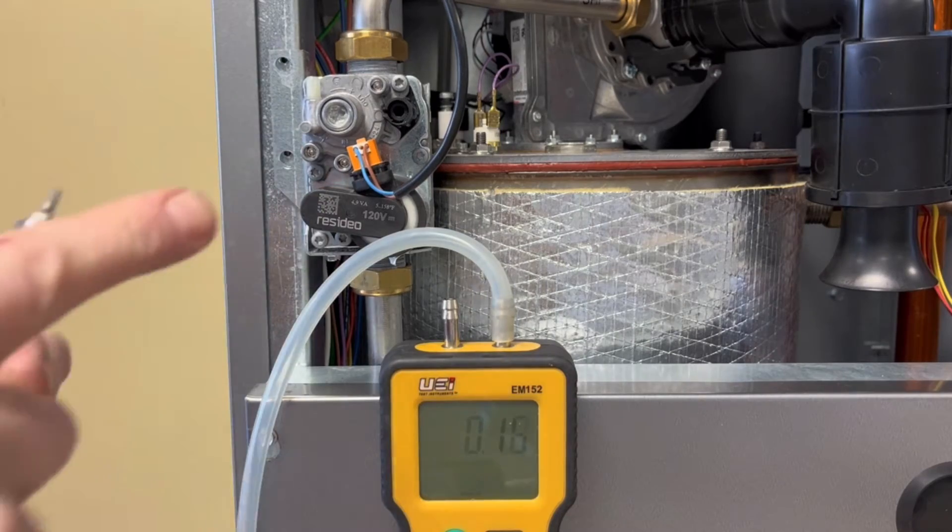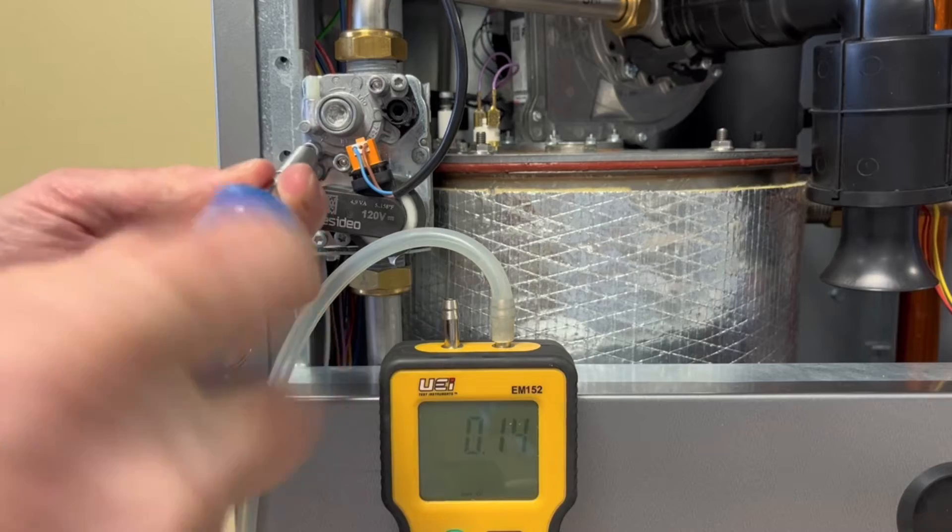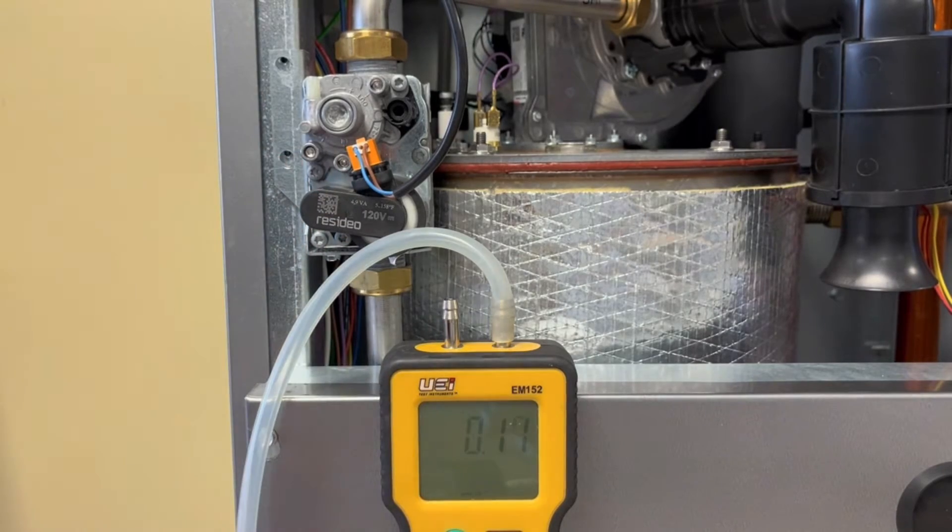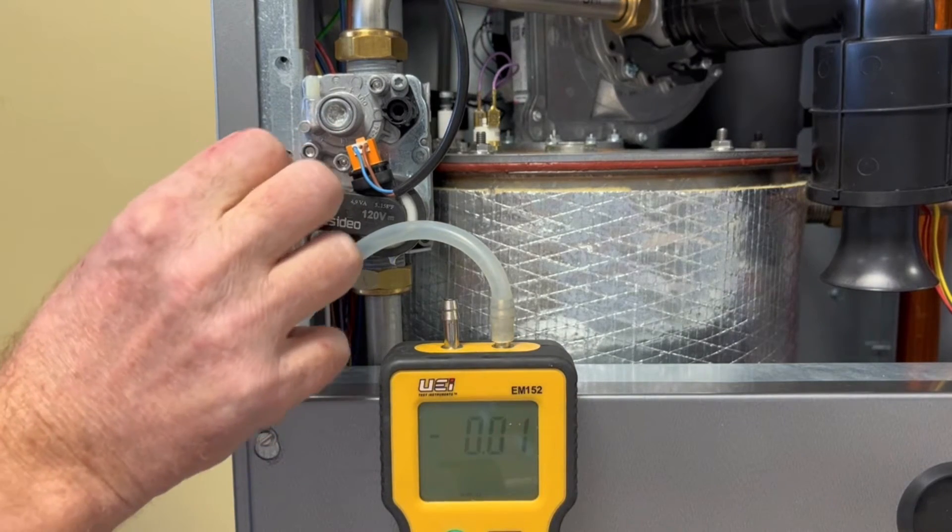To begin the gas valve reset procedure, connect your manometer to the R port on the left side of the valve. Do not remove the screw, just back it off approximately two turns and connect your manometer.